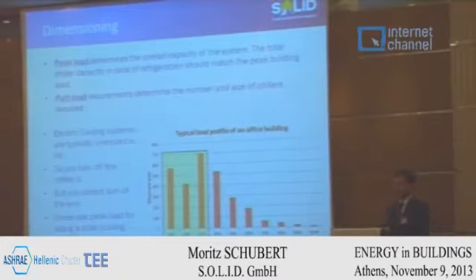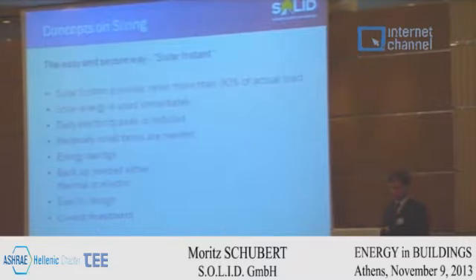like 700 hours per year, you only need 30% of the installed load, or even 20 or 10. As we have a rather high investment cost for our system, this investment can have the best payback if you have long operation hours every year. This is reached where the part load occurs, with long operational hours every year. The peak load, which is only a few hours every year, we leave to the compression chillers, because they are much cheaper to buy.